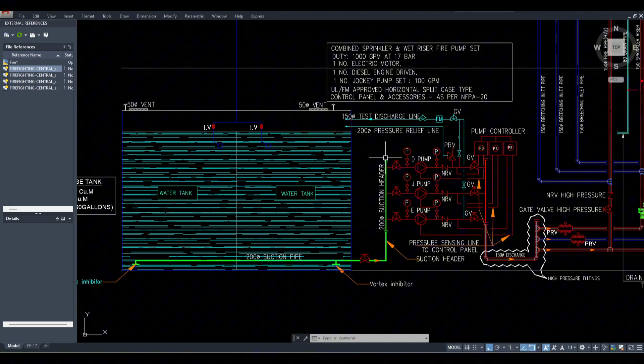Then you come to this line, and you get the line sizing. After that, you check that when the tapping comes out, immediately after each tank connection you must have an IV, isolation valve. If it's not there, it means you are doing it wrong. Then after the isolation valve, you go to the header, and from the header you get three kinds of pumps, so you need to check that all three pumps are available.